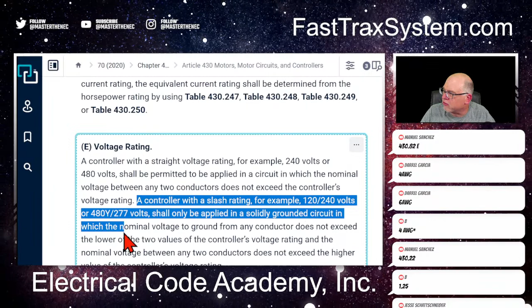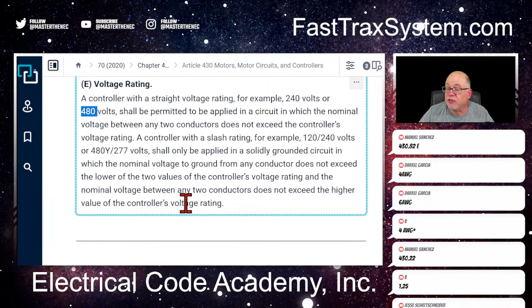Got it. A controller with a slash rating, for example 120/240 volts or 480/277, shall only be applied to solidly grounded circuits. All great information, but the key value for me is that a 480 is a straight voltage. With a 120/240 or a 277/480, the voltage to ground is 277, and 480 is phase to phase. So in a straight rated 480 controller, 480 to ground would be what? 480, right? A lot of words to tell you that. So come back to the lesson. Now, if this had a slash rating on this controller, then it would have been a different question. But 480, and there's your 430.83(E). Okay.